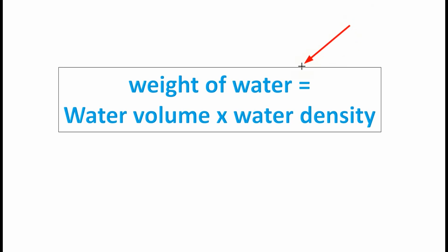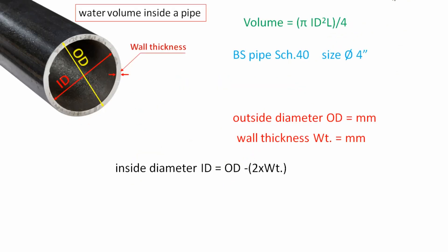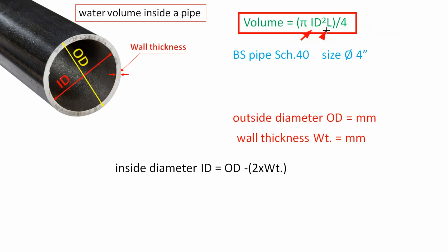To calculate the weight of water, first we calculate the volume of water inside the pipe, then we multiply it by water density. To calculate the volume of water, we use this formula: volume equal to pi into inside diameter squared into pipe length, divided by 4.